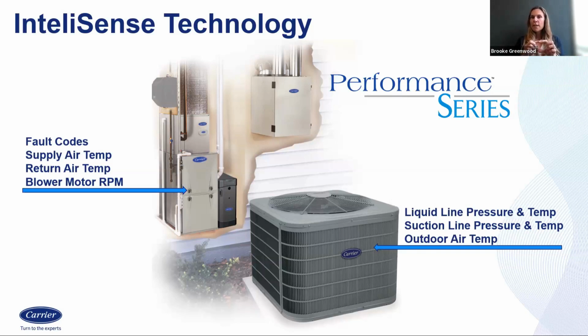When you're configuring the furnace, it will move through menu items automatically - I don't want to say scrolling, because I don't want people to think the 7-segment display is scrolling, although you might see that on our Infinity line, which is a great new feature. It will scroll through the items, flash SAT and a temperature, flash RAT and a temperature, and then flash delta T and a temperature - calculating your delta T for you on site while the power is applied and the system is running. You'll be able to pull some of that information into the app with near field communication.